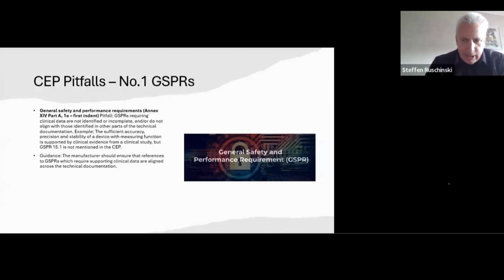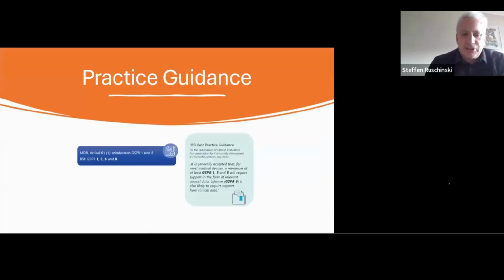In practice, according to MDR Article 61.1, we need at least GSPRs 1 and 8. There are still exceptions where we don't need them after Article 61.10, but in practice, we can always recommend also using GSPRs 5 and 6, meaning mistakes by the user. For example, if you have risky products that are used by non-professionals, like blood sugar measuring. And GSPR 6 is safety and performance throughout the whole lifetime. For example, if you have implants in the body of a patient that are not intended to be taken away after some time, then this lifetime still has to be the same as the remaining lifetime of the patient.